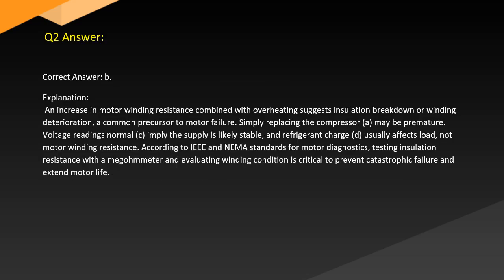Answer. Correct answer: B. Explanation. An increase in motor winding resistance combined with overheating suggests insulation breakdown or winding deterioration, a common precursor to motor failure. Simply replacing the compressor (A) may be premature. Voltage readings are normal, so C is unlikely, as the supply is likely stable, and refrigerant charge (D) usually affects load, not motor winding resistance. According to IEEE and NEMA standards for diagnostics, testing insulation resistance with a megohmmeter and evaluating winding condition is critical to prevent catastrophic failure and extend motor life.